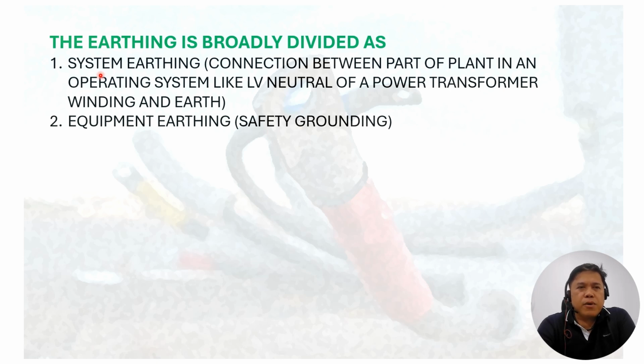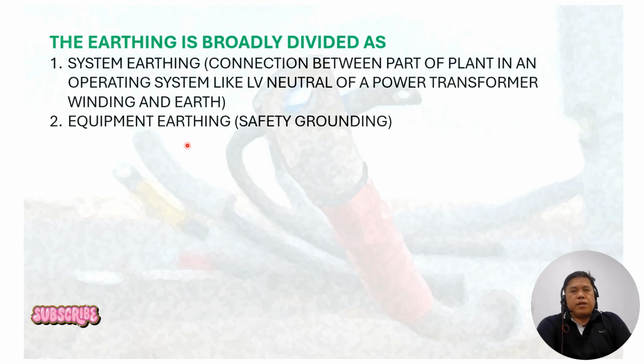That's why we're calling it system earthing, the connection between part of the plant and operating system, like LV neutral or power transformer winding and earthing. Number two, equipment earthing, that is safety grounding.